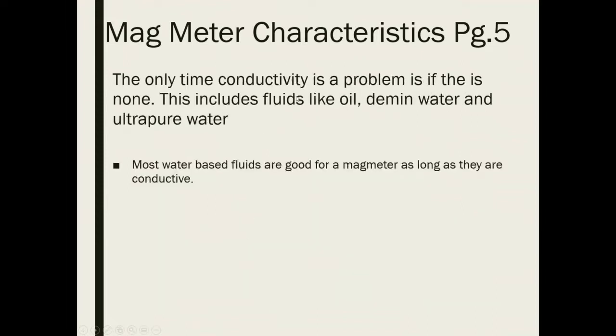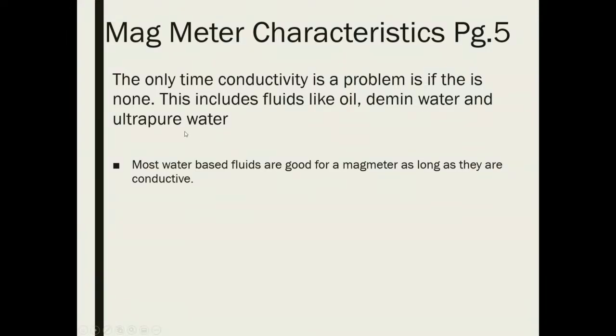The only time conductivity is a problem is if there is none. This includes fluids like oil, demineralized water, and ultra pure water — those are the problem children for mag meters. Most water-based fluids are great for a mag meter as long as they are conductive. Demin water and ultra pure water would usually only be seen in steam-type applications.